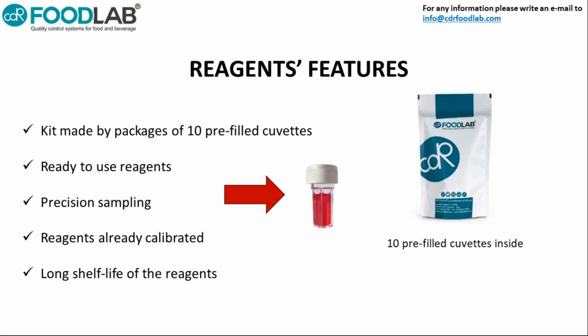What about the reagents? As I told you, we develop and produce our reagents, and we calibrate our reagents on our machines. The specific kit is made of a package with 10 pre-filled cuvettes inside. As I told you, the pre-filled cuvettes are ready to use. We have, of course, precision sampling using a pipette. In this case, we use a normal air pipette for the beverage part, while we use a positive displacement piston pipette for oils and fats. Okay.